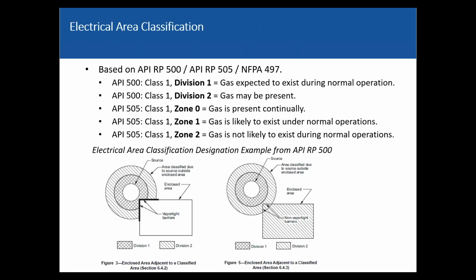All right. Okay, now electrical area classification. So we talked about API 500, and the difference is Div 1 says gas is expected to exist during normal operation. So if this is an example, and here's our gas source, this would be like a Div 1 boundary. Div 2, gas may be present, so it's a bigger boundary. And then 505 is different in that Zone 0 says gas is always present. So they just classify it a little differently. Zone 1, gas likely to exist. Zone 2, gas not likely to exist. I'm not exactly sure why there are two different documents, the Div and Zone ones, but there are.